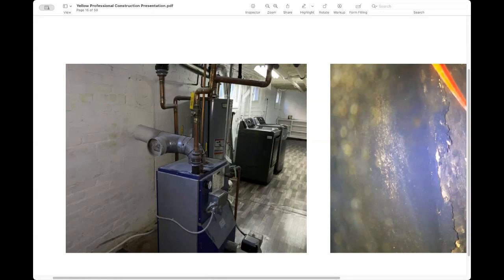Barometric damper. Allowing airflow? It protects the burn chamber of the piece of equipment, because when high volume breeze or wind runs across the top of the chimney, you get a suctioning effect. And if you pull really hard, you may have seen a fireplace where it flares up and then calms back down when the wind dies down.